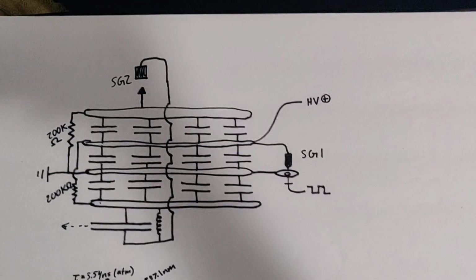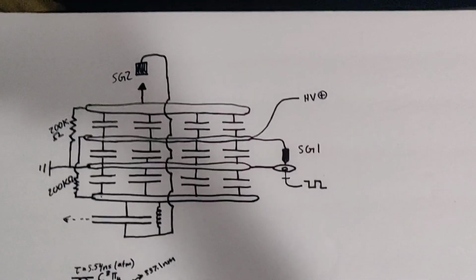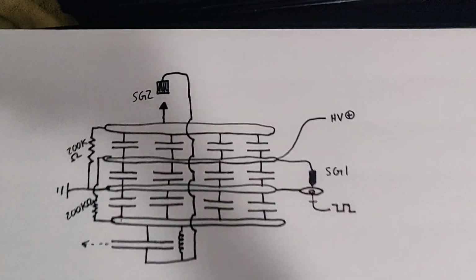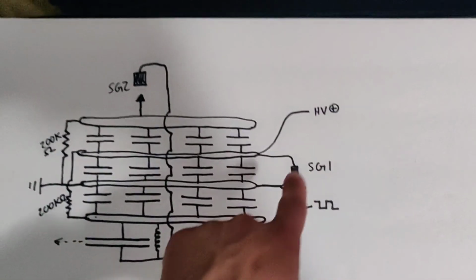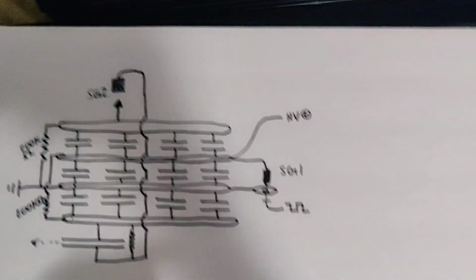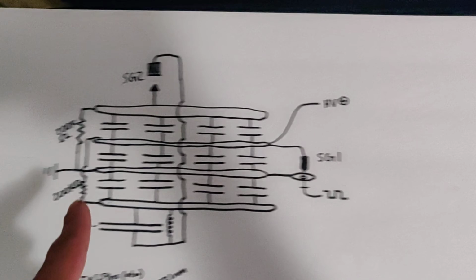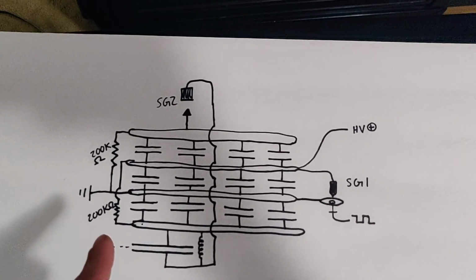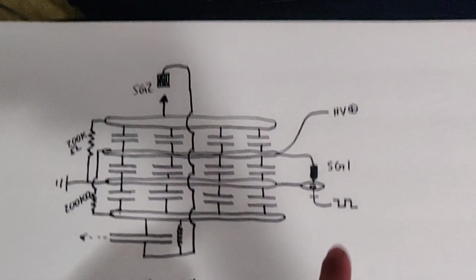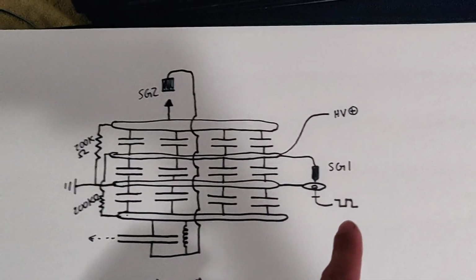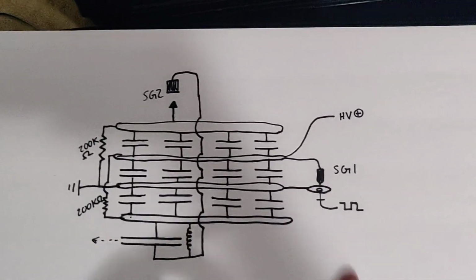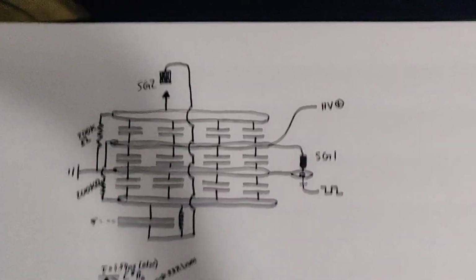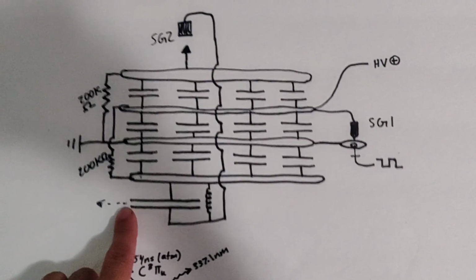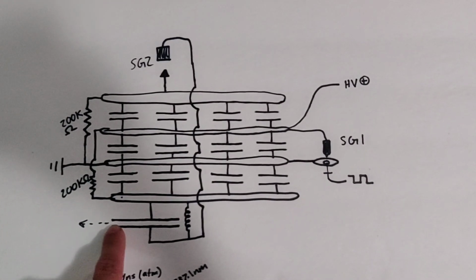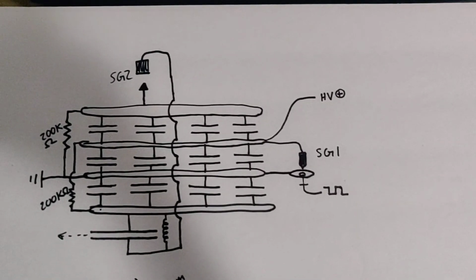has a set of 24 capacitors in total. The circuit is doubled, and two spark gaps. You can see spark gap 1 and spark gap 2, as well as a high voltage input, a ground, two 200 kilo ohm resistors, a small inductor, and an input pulse of moderately high voltage, about 1 kilovolt, I think. And then you have two transverse electrodes which excite the gas in between and then produce the laser beam.